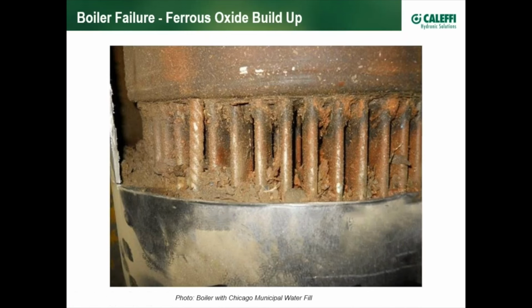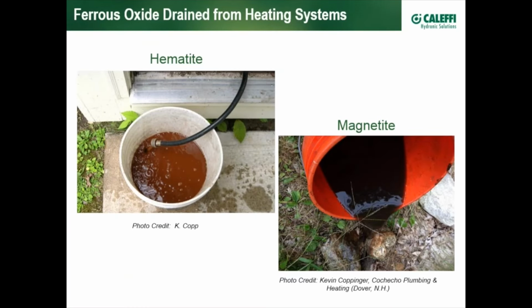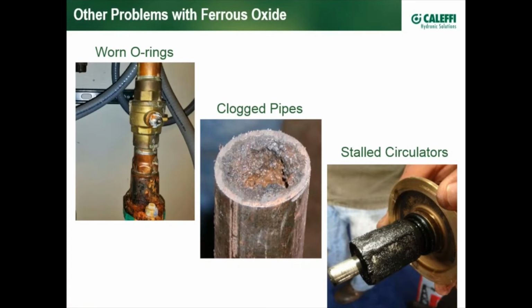Here's another example on a condensing boiler. This is a fire tube boiler which has succumbed to ferrous oxide buildup. Here is a shot from a contractor who had problems with a system that had oxygen ingress and resulting corrosion, hematite, magnetite. Magnetite is the more common, kind of the, as contractors will say, the black ink that they see oftentimes. Now, no worries with pouring this into the earth. Magnetite is a naturally occurring substance in the earth. As an example of magnetite, you might remember from science days, is something called lodestone. It's basically a magnetized magnetite. Early compasses were made out of lodestone.